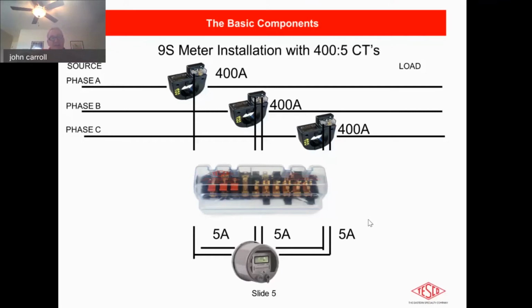But the idea behind this is really just to give a 5 amp current to the meter, which makes it a safe environment to do operations. And the ratio of that value, which in this case is 80 to 1, is very much the measurement capability here. That's what's going on with the ratio, and that's why we need to measure these on a reasonably regular basis.